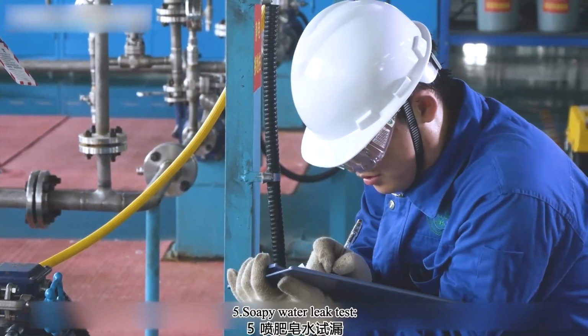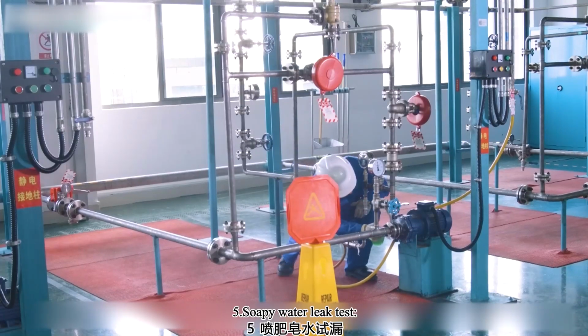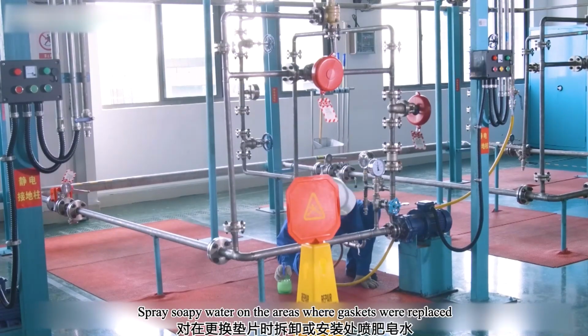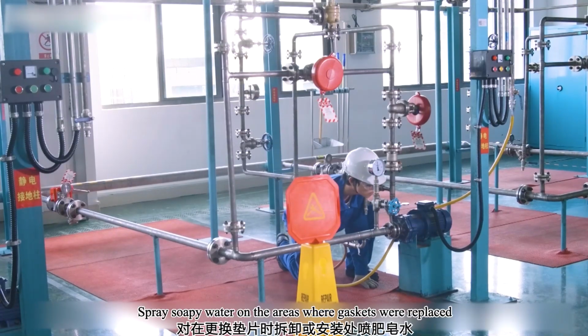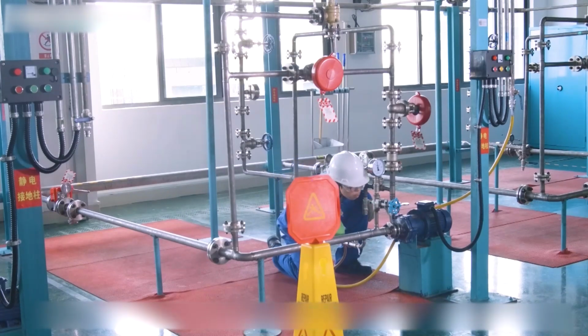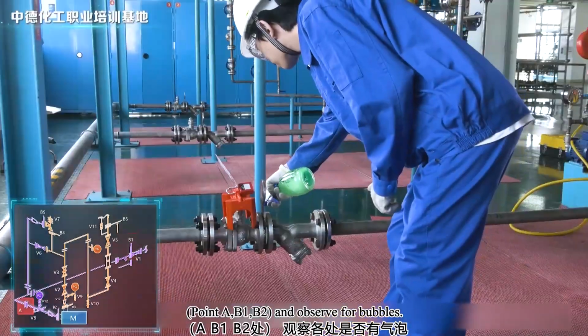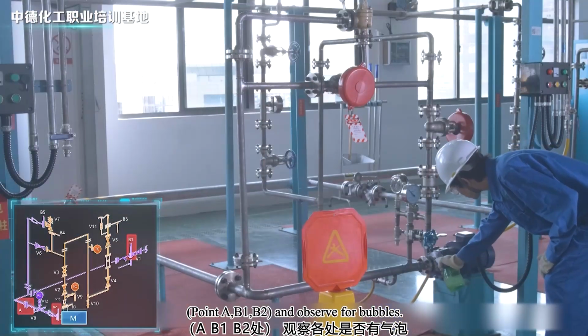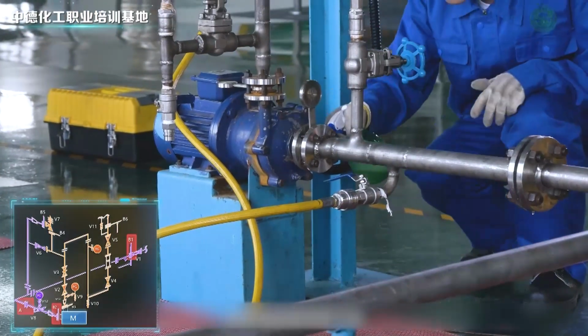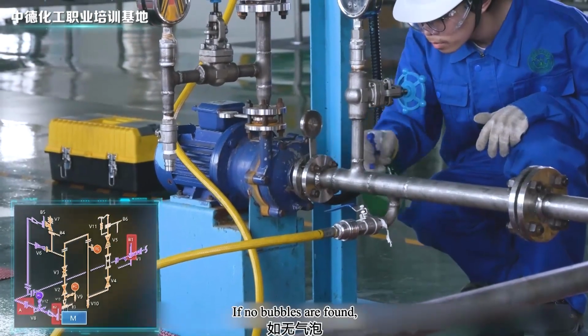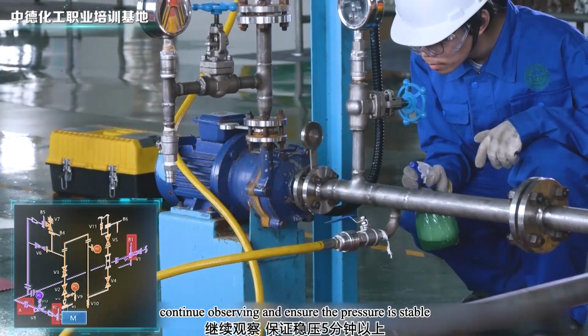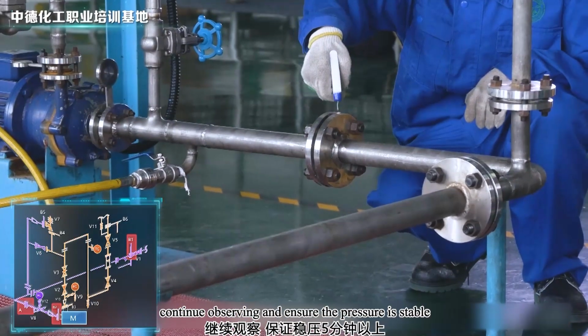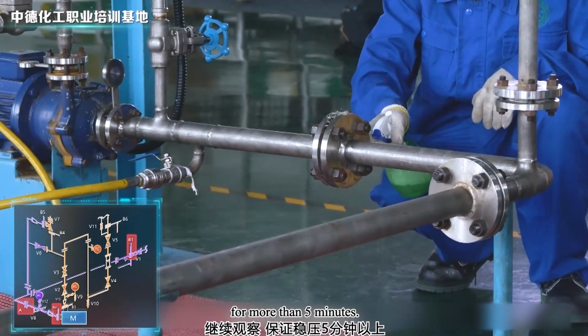Fifth, soapy water leak test. Spray soapy water on the areas where gaskets were replaced or reassembled. Points A, B1, and B2, and observe for bubbles. If no bubbles are found, continue observing and ensure the pressure is stable for more than 5 minutes.